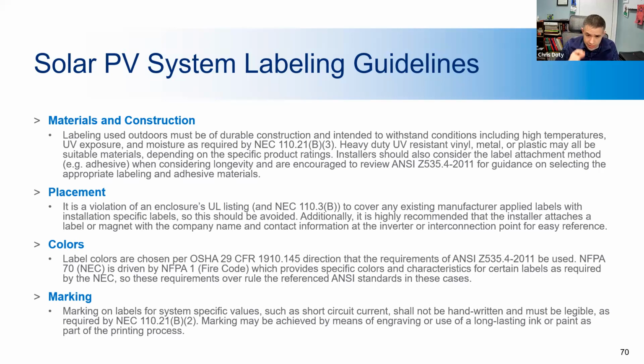The other thing to keep in mind is the most dangerous label is a wrong label. If you have a missing label, that's bad, and it's not very safe. But if you have a wrong label, that's even worse, because if you have an electrician coming to work on your house, they'll see that label and think they know what the situation is. If it's not that, they could potentially do something harmful, put themselves in harm's way, and cause shock hazards and injuries. So you definitely want to make sure that all the labels are correct.